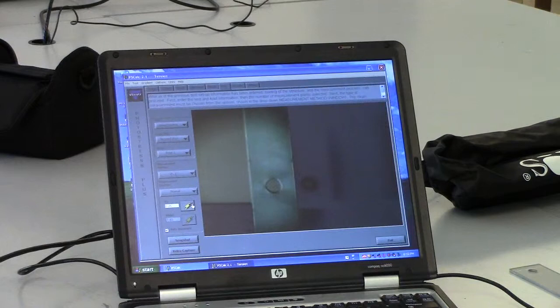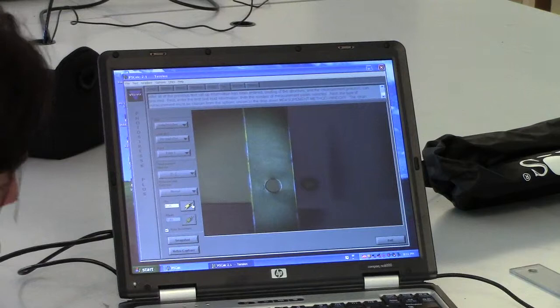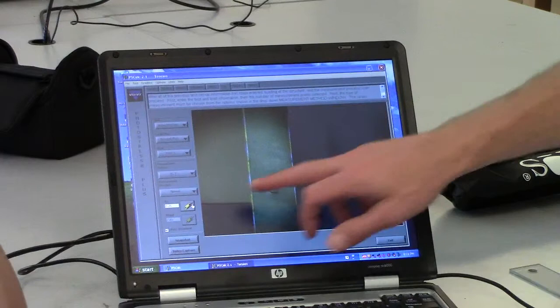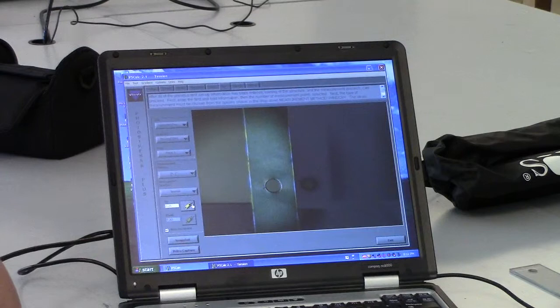Remember, this software has no idea what's going on with the load. I'm still doing the same thing. This is on zero, and I'm going to hit the little lightning bolt. Does that make sense, how it doesn't matter what's going on over there? All I'm doing on this first setting is making sure this is zero and recording that. As long as you are good with that being zero, we now hit the lightning bolt by R0.